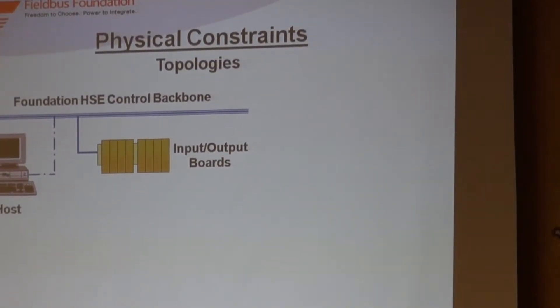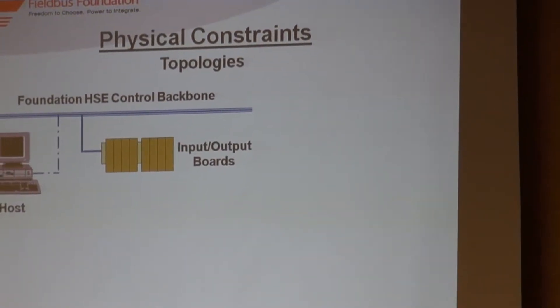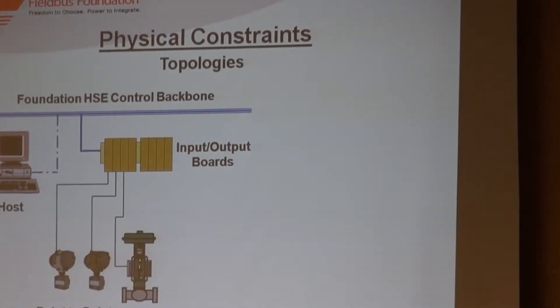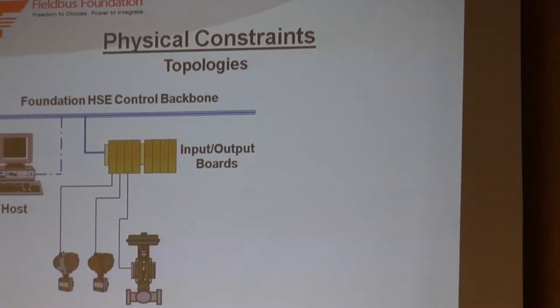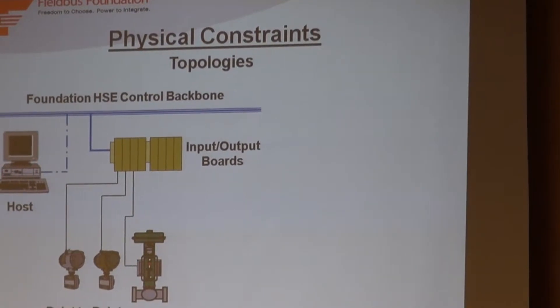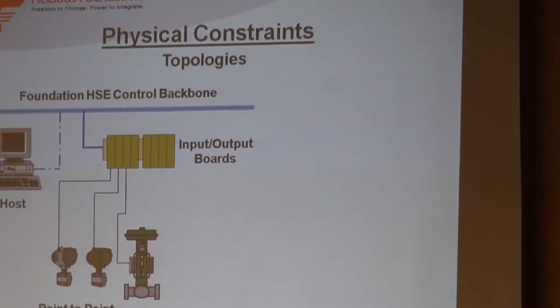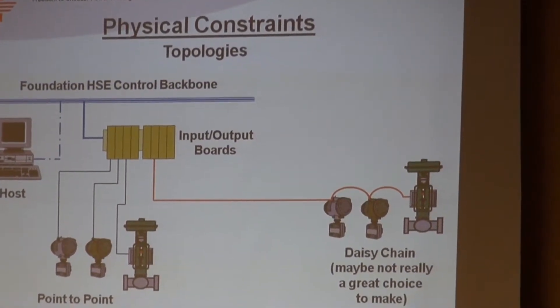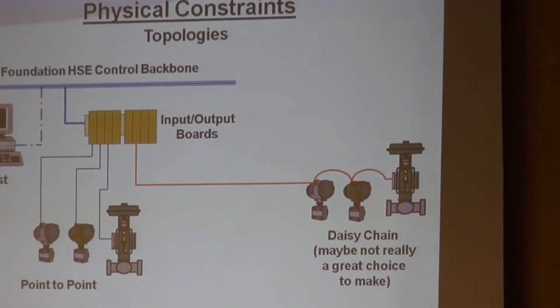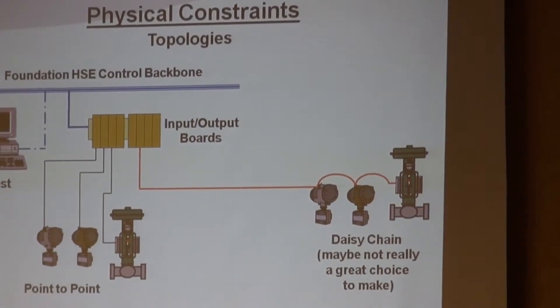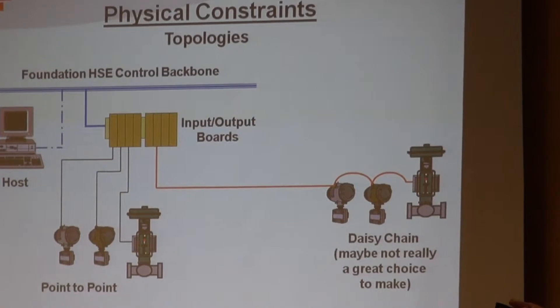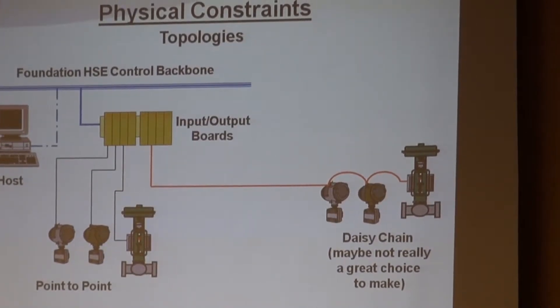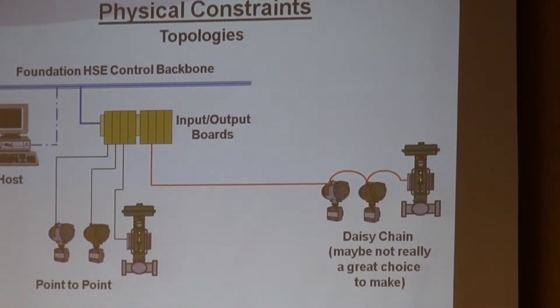Let's build one. You start up with your host, and it's got its own input and output boards - we'll call them H1 interface or a linking device or whatever. You can have point-to-point. Is that really practical? No, not really, but you can do it. You also have daisy chain. Is there any reason why you should not do that? Take one device out and everything downstream goes down. There may be occasions where that's okay, if you've got a loop that's totally independent and if something goes down, so what. Usually, don't.